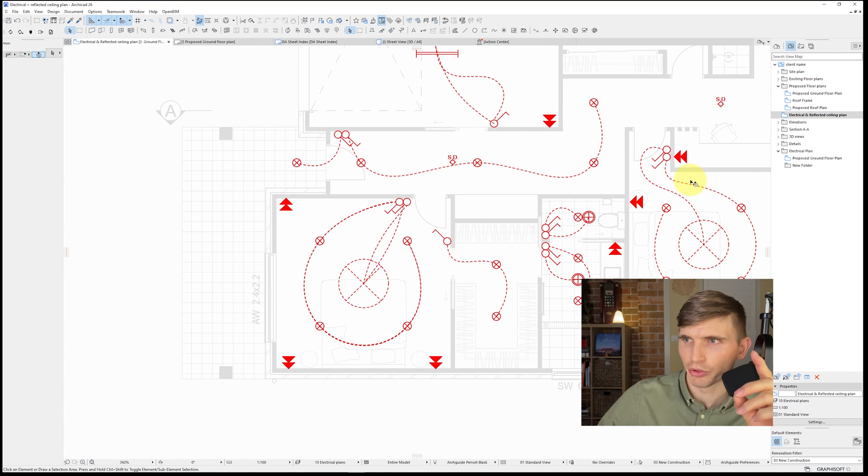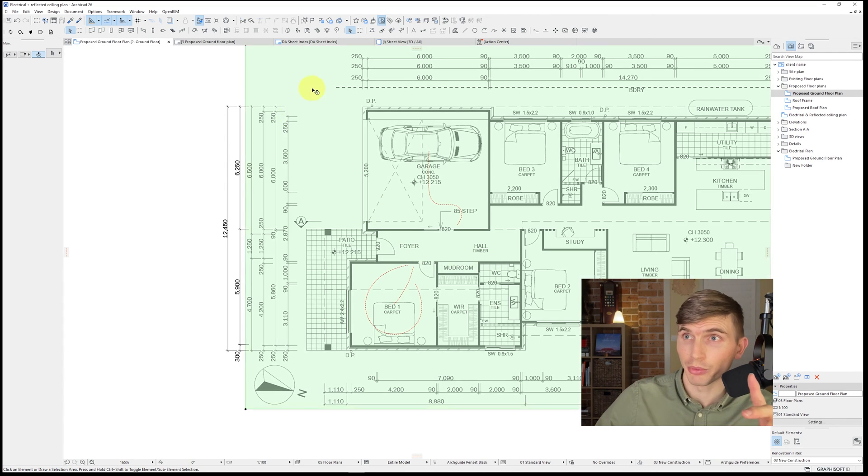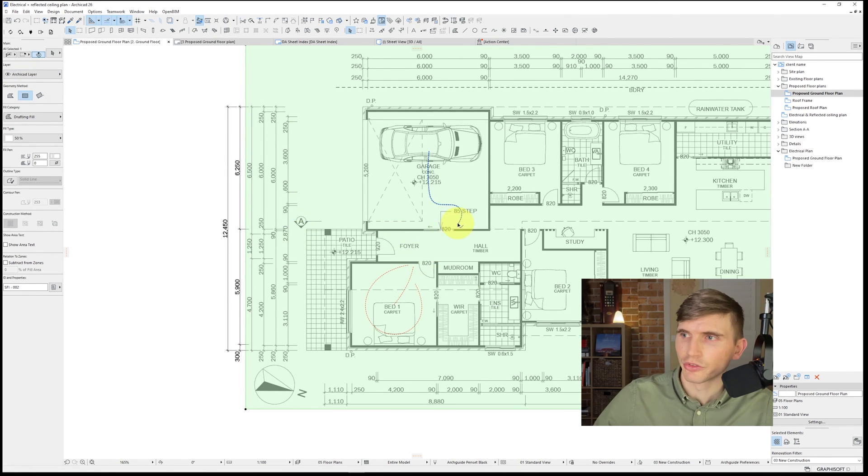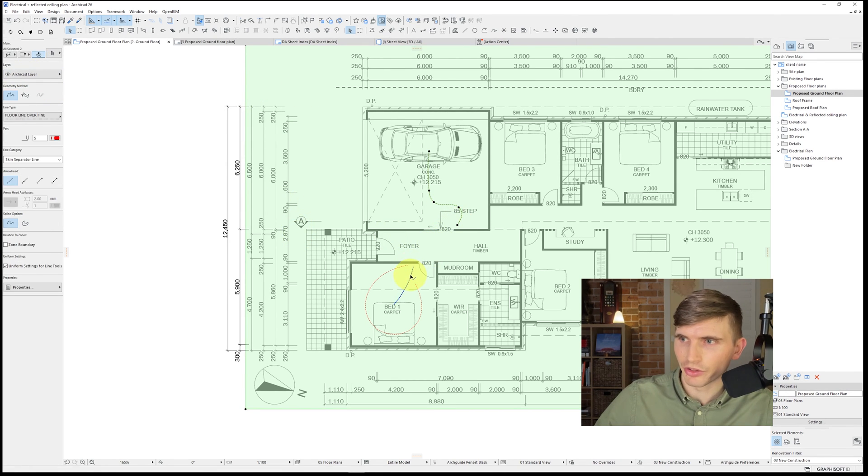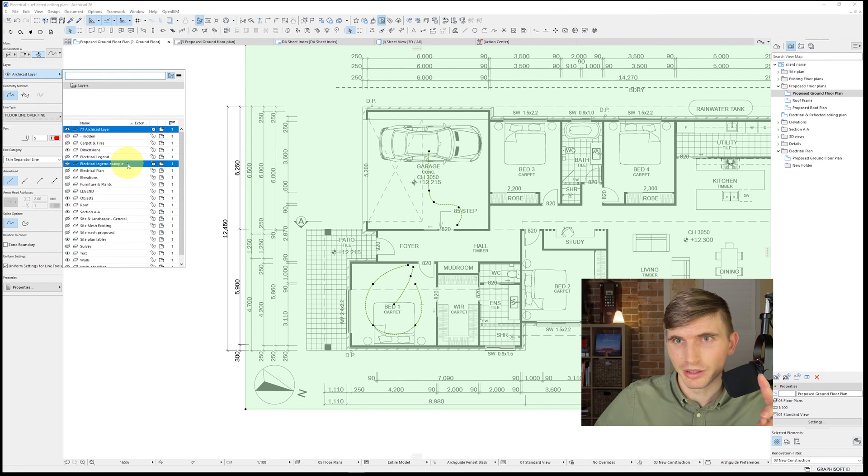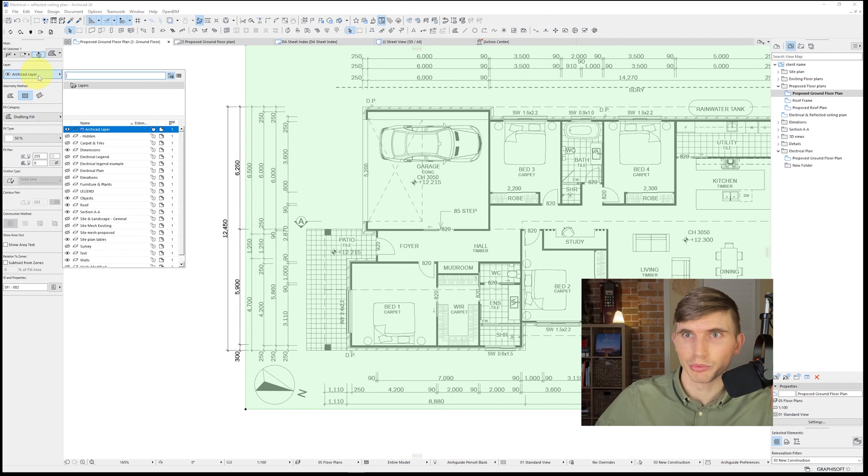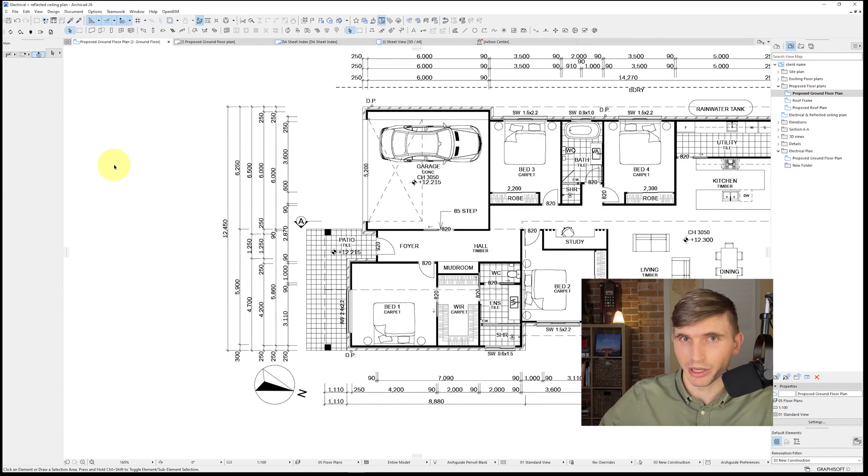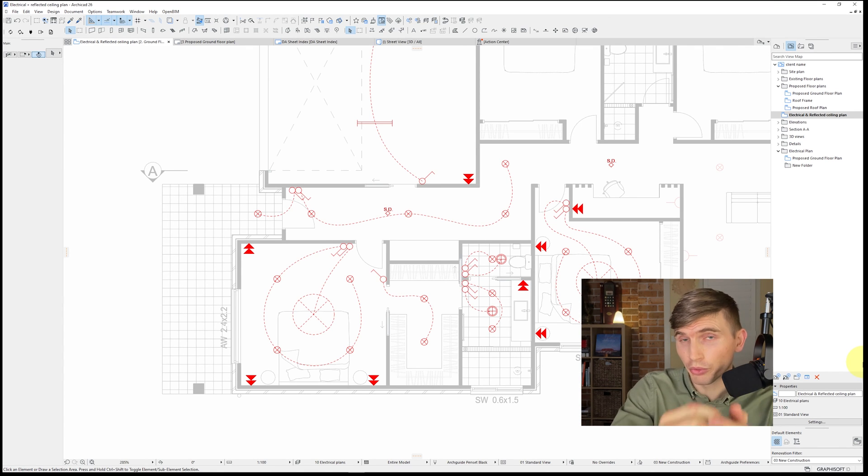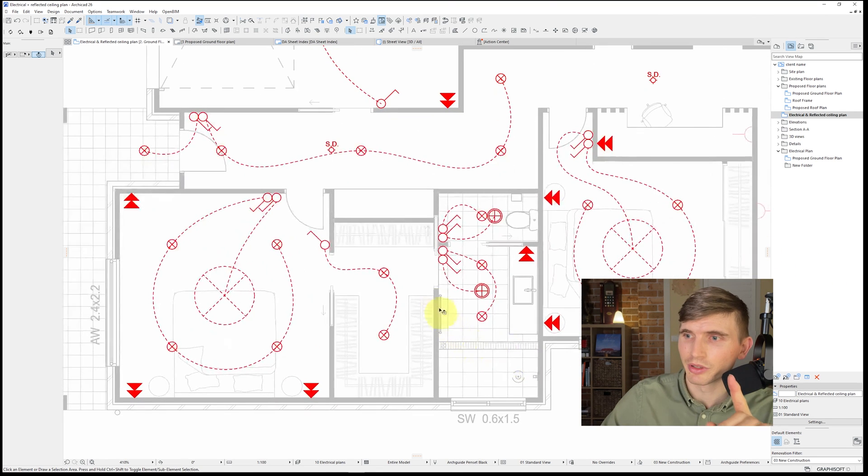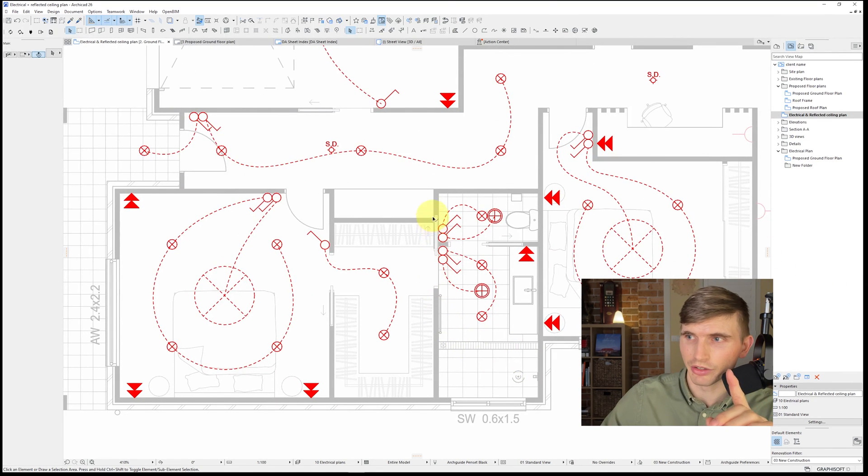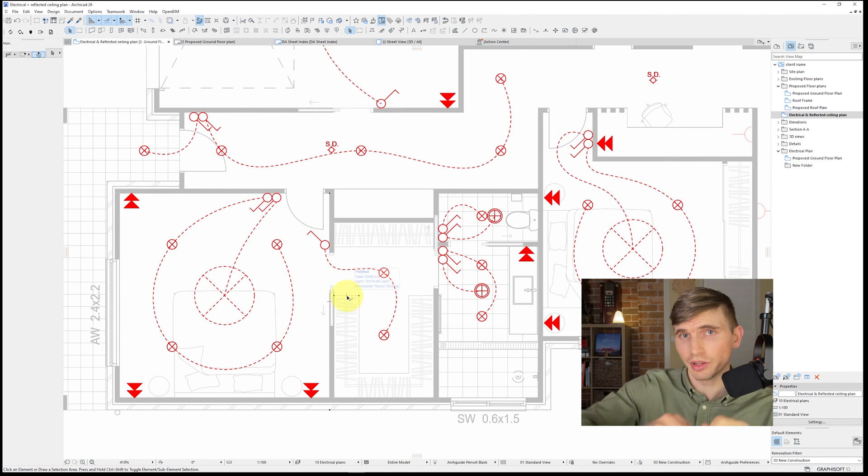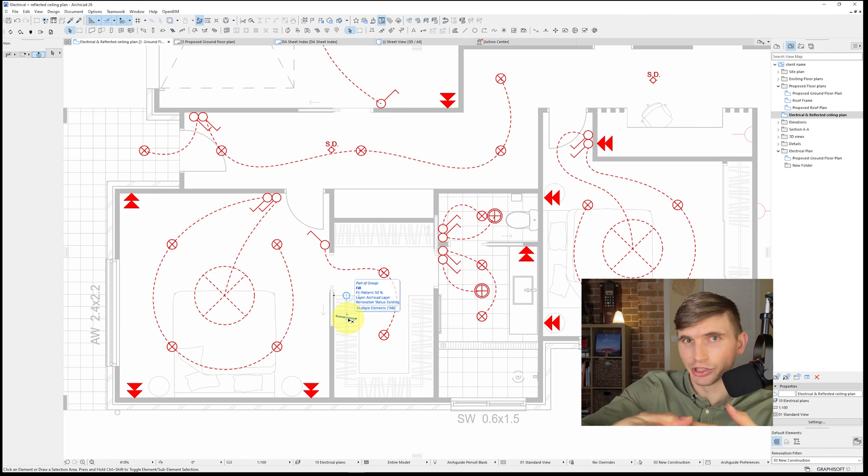All right, let's just go back through to our example. If we just go back to our floor plan, we'll notice that we haven't set our fill to the correct layer. So it's going to be showing over the top. So let's select all the things that we didn't set up correctly to begin with and we'll select those to the electrical legend example, which is going to make those disappear. Any thing is, we can do this after. So not everything has to be perfect straight off the bat, takes a bit of the pressure off. Each house is unique. So from here, you'll just need to go through applying each of the different elements to the rooms accordingly. One other little thing to watch out for is cavity sliders. You'll want to make sure that your lights are set on a wall where the cavity isn't behind. This is so that the cabling can go down through the back of the stud and the cavity isn't jamming up against the cords.